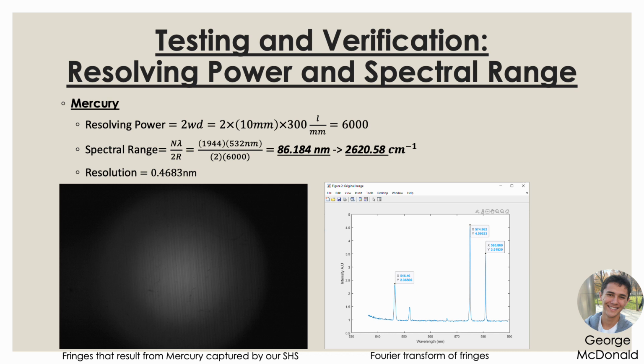So here are the results involving our measurements with mercury. The resolving power still remains about 6,000 because, due to the input collimator optic that we have, the beam size is about 10 millimeters. When we used it with Krypton, the beam size was roughly the same. But here in this case, the beam size is still approximately 10 millimeters, which results in a resolving power of 6,000.